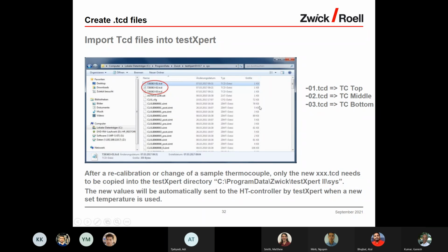After recalibration or change of a sample thermocouple, only the new .tcd file needs to be copied into the testXpert directory. Here I say the sys file. The new value will be automatically sent to the high temperature controller by testXpert when a new set temperature is used. This is as simple as it is.